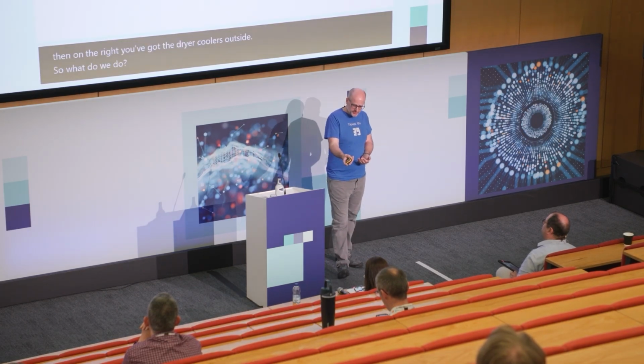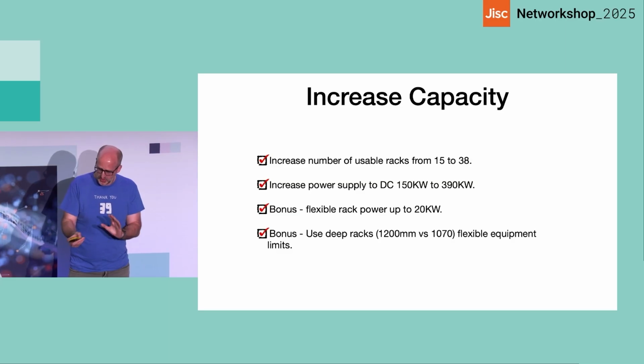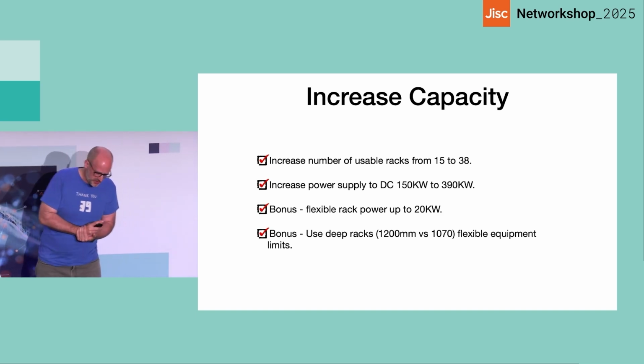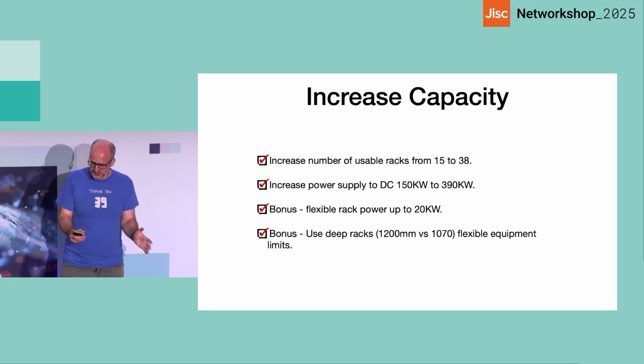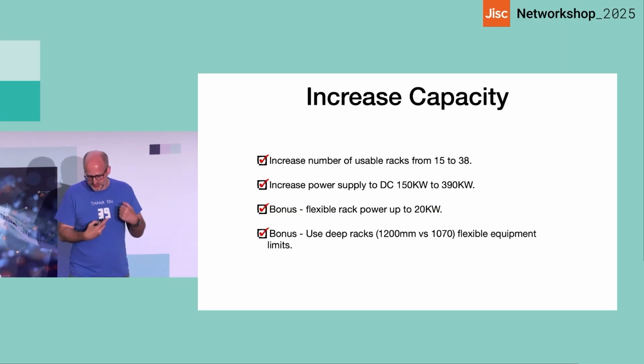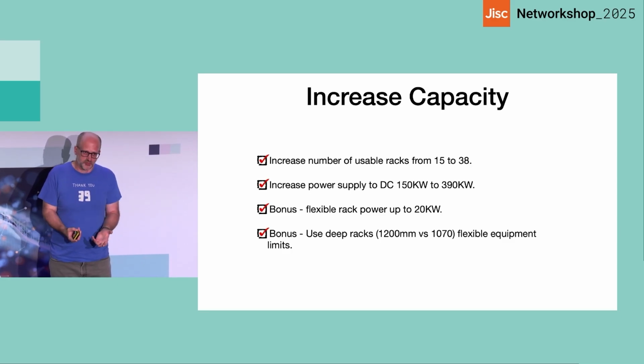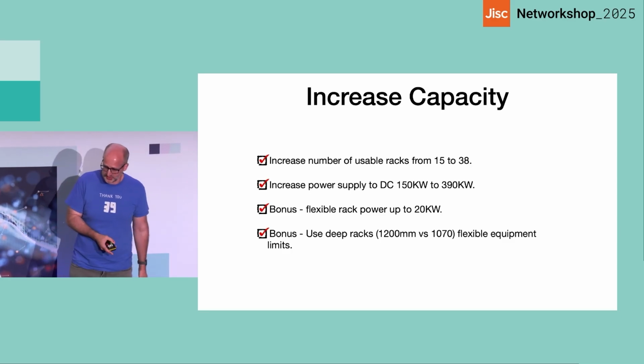So what did we do? We increased the capacity of the room. We had 15 racks, and we went up to 38 usable racks. One of the racks has a bollard in the way, fortunately, for the building. We went from a nominal 150 kilowatts in the room to 390. We've got a flexible rack, so we can go up to 20 kilowatts a rack. And the original racks in the room were only 800 mil deep when they were first built. We now have 1200 mil deep, which is much more useful for modern kit, because a lot of modern kit needs 1200 millimeter deep racks.